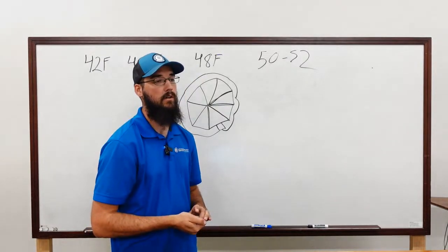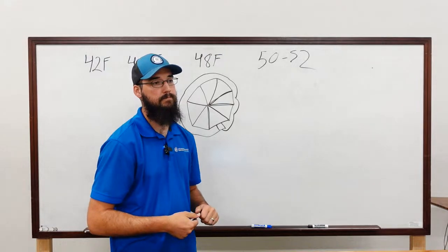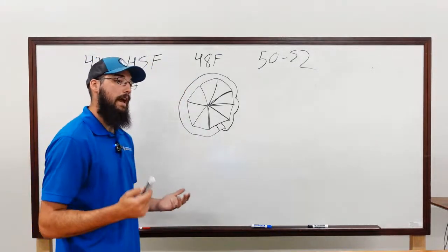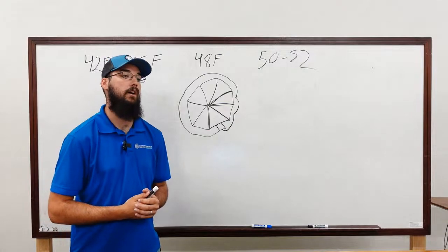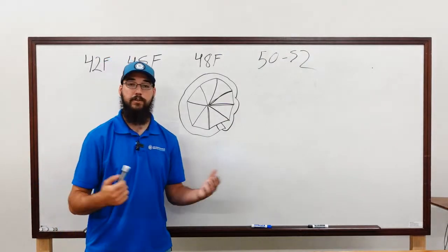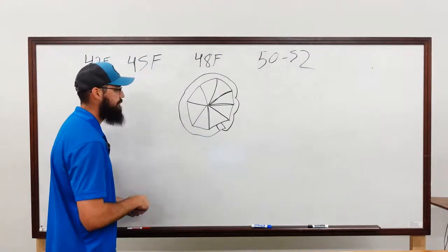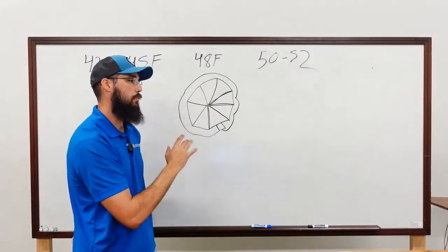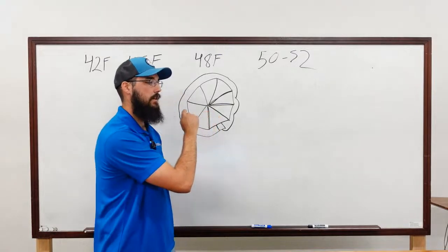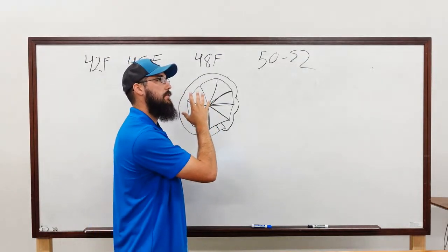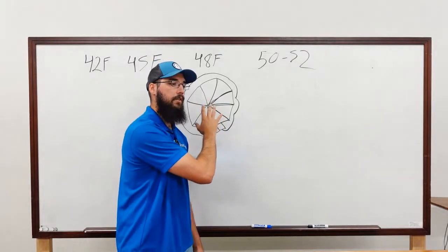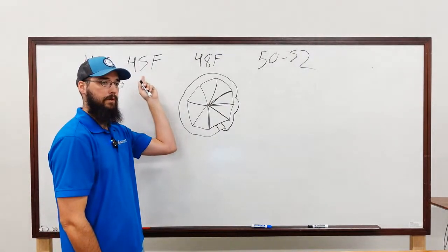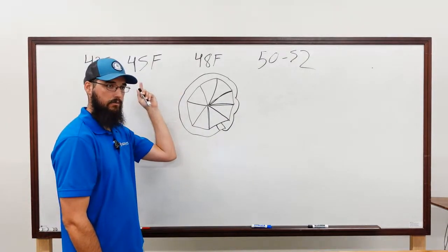If you put the current limiter on, say you set it for 60%, is that automatically going to dictate how far those vanes open and close? Yes, and that's actually a wonderful segue. Let's say we have a pull down sequence that the chiller goes into at startup, which it should. You want your chiller to have that. It's going to limit how much these vanes open, because two things decide, or really it's more than that, but this is where we start talking safeties. One thing that controls the vanes is deviation from set point. We need to get to our set point. Depending on how we're deviated from it will depend whether we open or close.